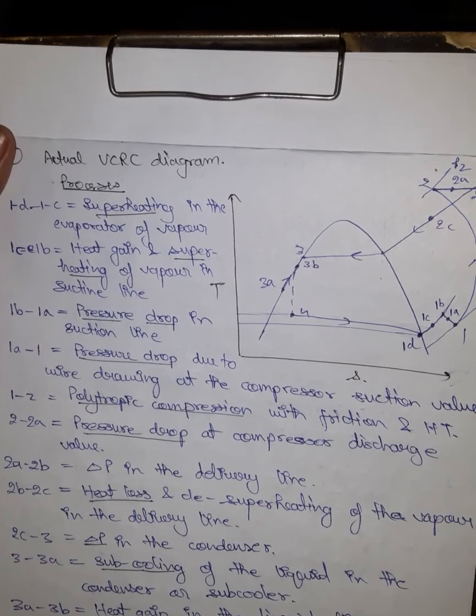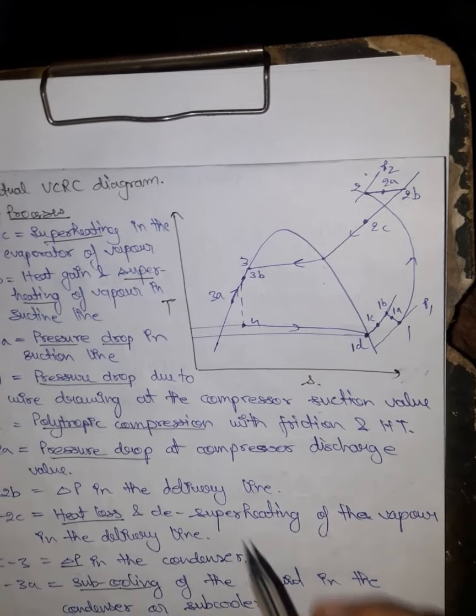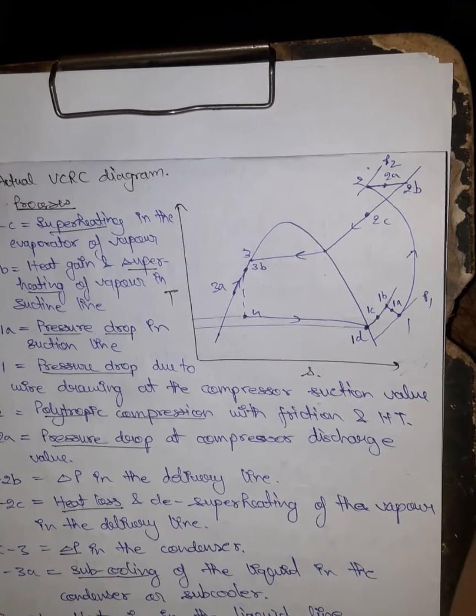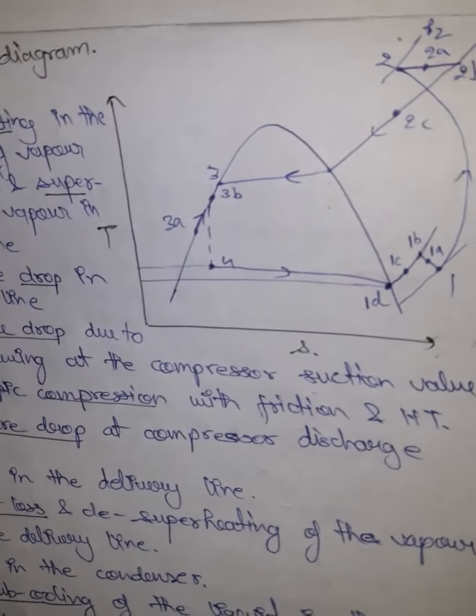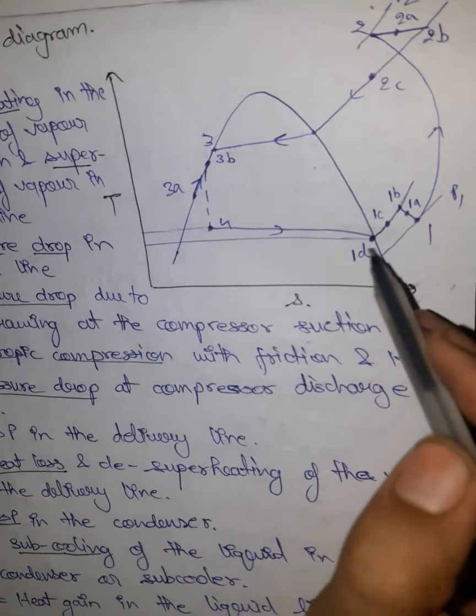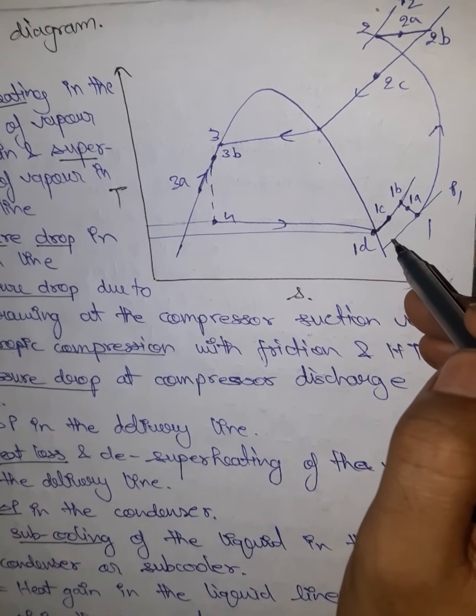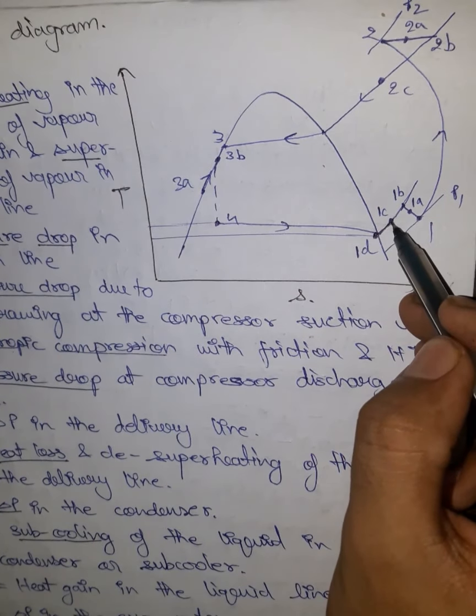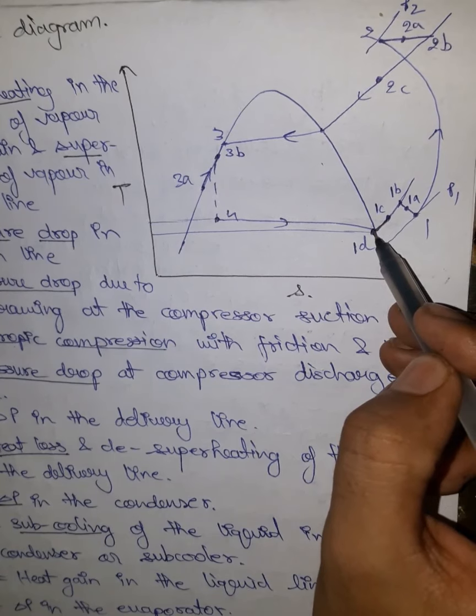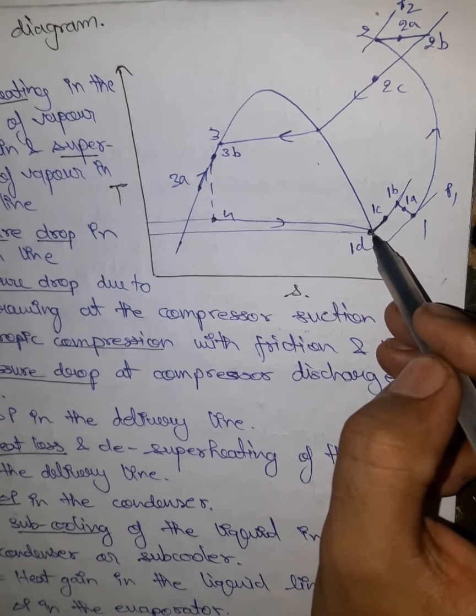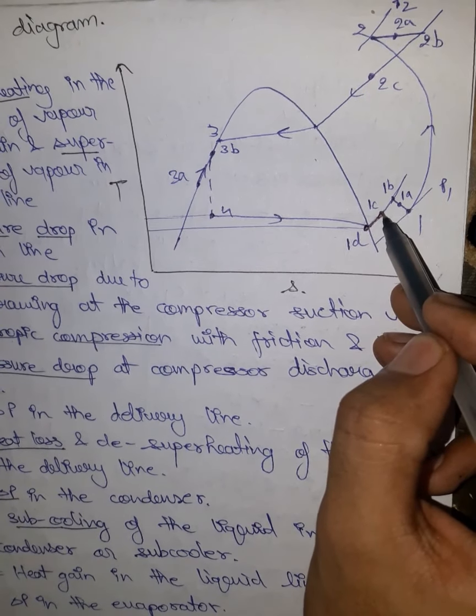I have noted down the various types of losses that are occurring and we will discuss each of them one by one. Correspondingly, I have drawn the TS diagram and will be drawing the PH diagram alongside. We start from point 1d. From point 1d to 1c, superheating is occurring in the evaporator itself — meaning the state we actually reach is not only saturated vapor but includes some superheating within the evaporator.